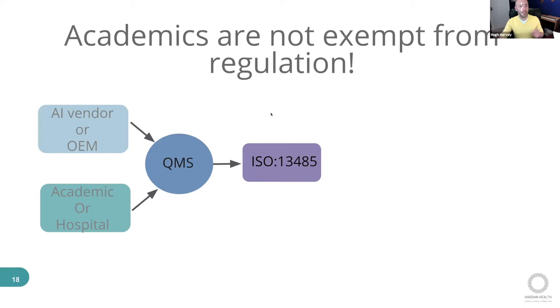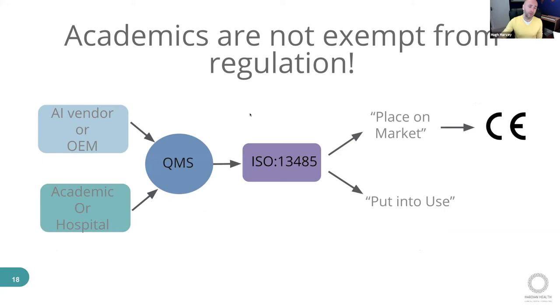And just for the academics watching, you aren't exempt from regulation. You might be thinking, well, I don't want to sell my product - that doesn't matter. In the EU, if you want to place it on market, that means to sell it, then you need a CE mark. But if you want to put it into use, you still need to get audited for what's known as ISO 13485, which is quality management systems, because we don't just want academics putting their, let's face it, non-productizable code directly into hospitals without any regulatory oversight. So academics still have to, in Europe, go through some regulatory scrutiny.